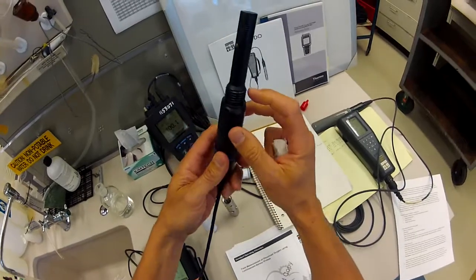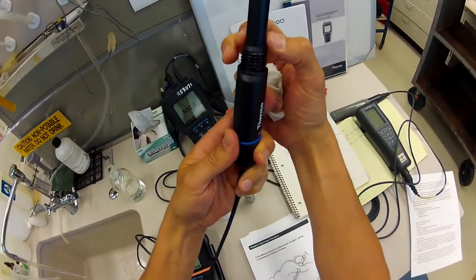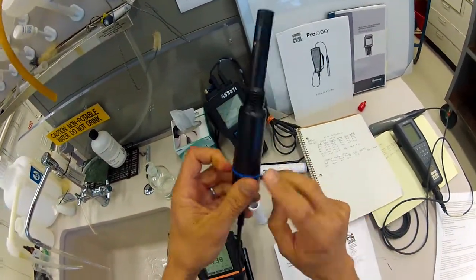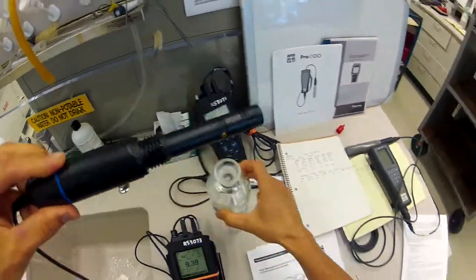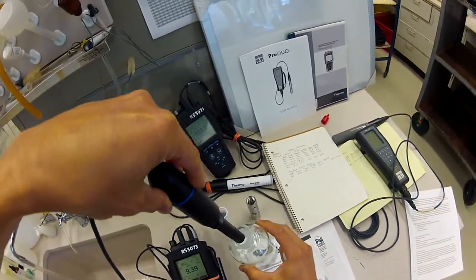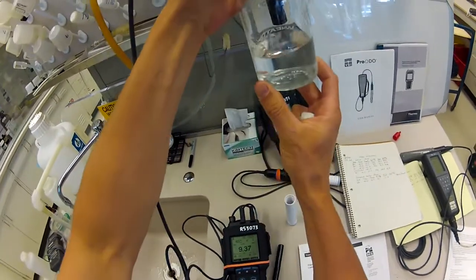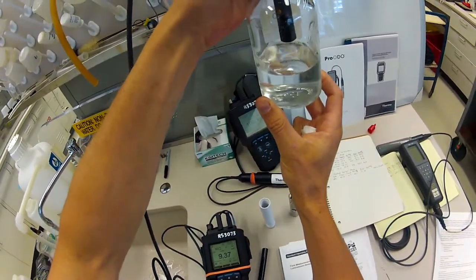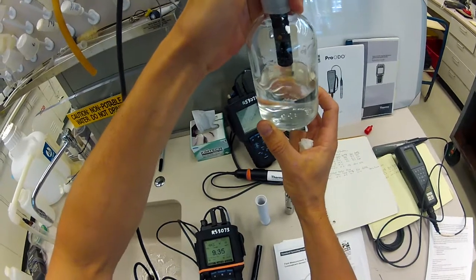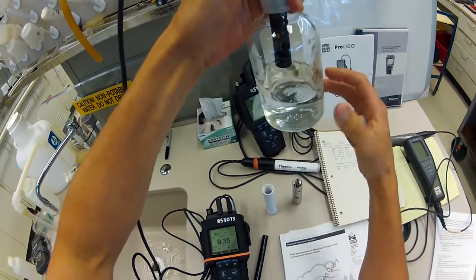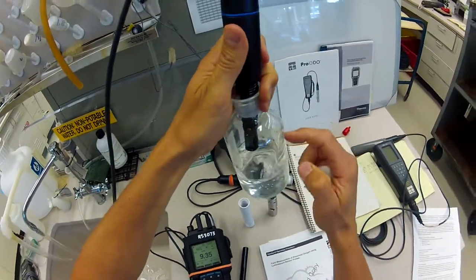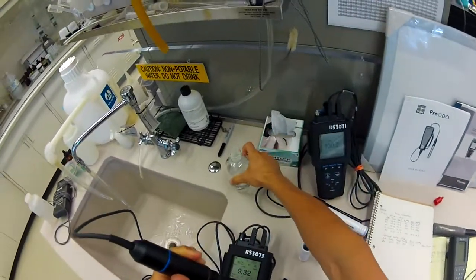The probe itself usually has some sort of little shoulder here and neck, and that will generally allow the probe to slide into a 300 milliliter BOD bottle like so. And you can use this either for making measurements if you fill it up high enough, or you can actually use this as a calibration chamber if you need to as well.